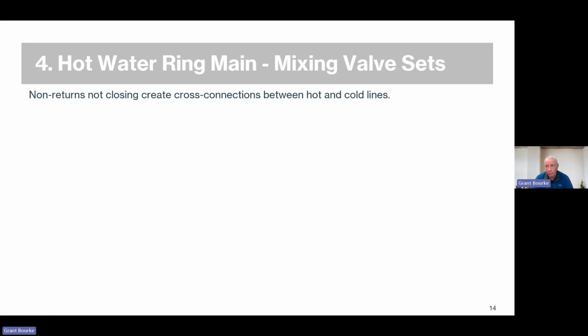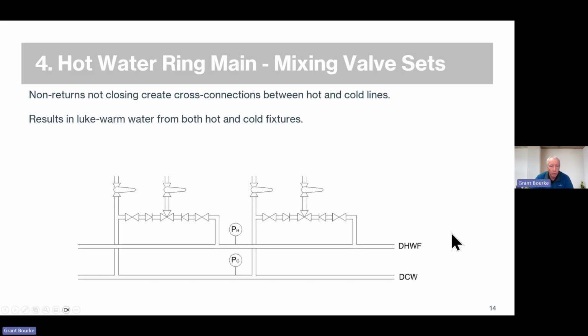You don't want to have one with a mixing valve one side only, you need both sides. Now this results in cross connections when the non-returns stick open over time. And I've spent many glorious hours crawling around buildings looking for the mixing valve that's causing the cross connection. So if we look at this pair of offtakes from the ring main here, we've got this non-return here. Let's say that is stuck open.